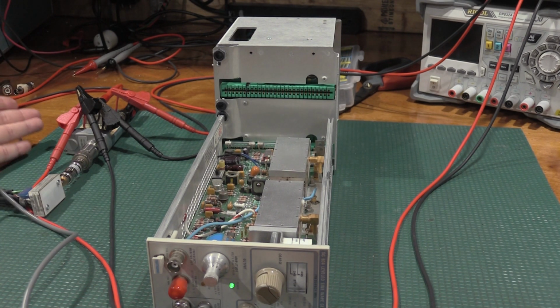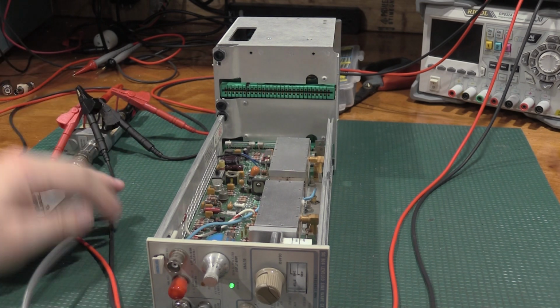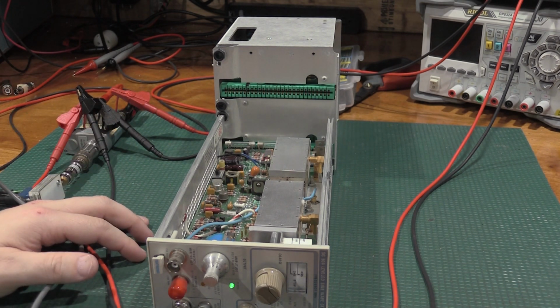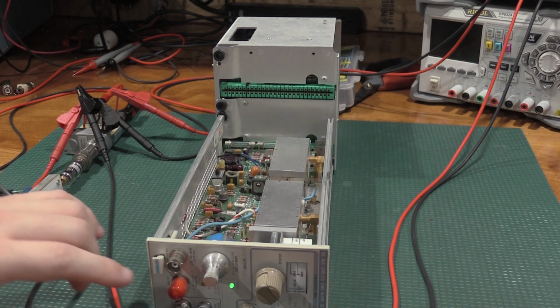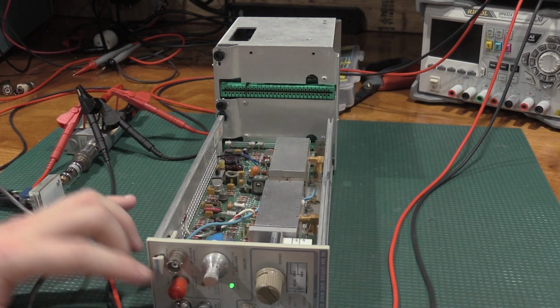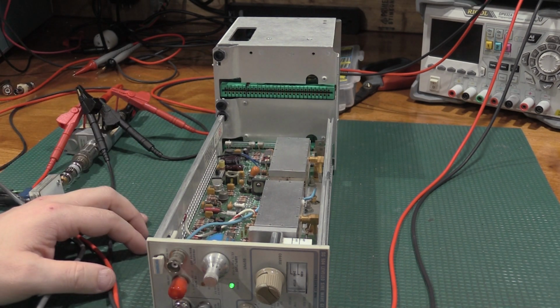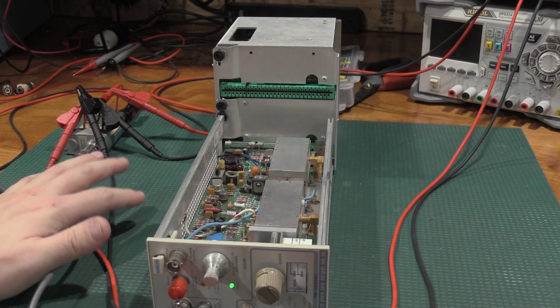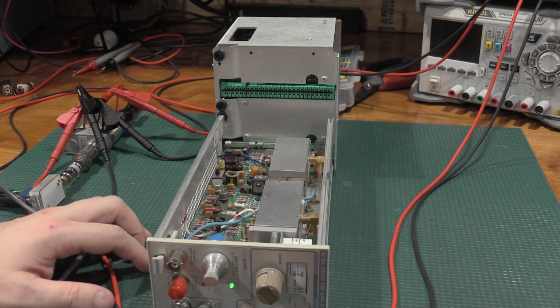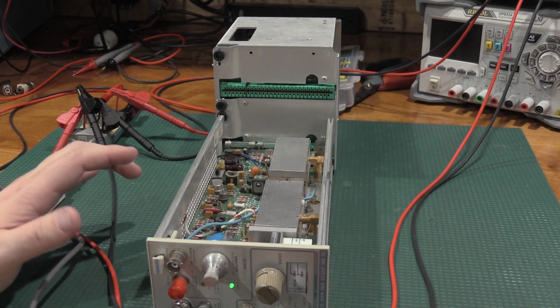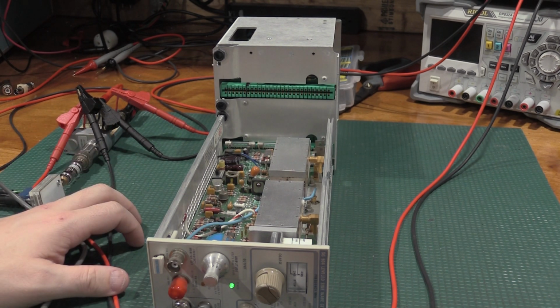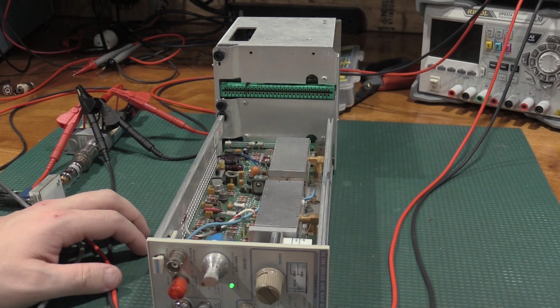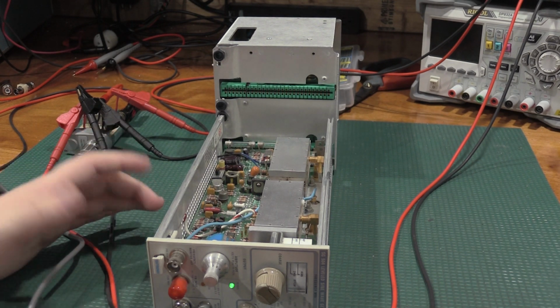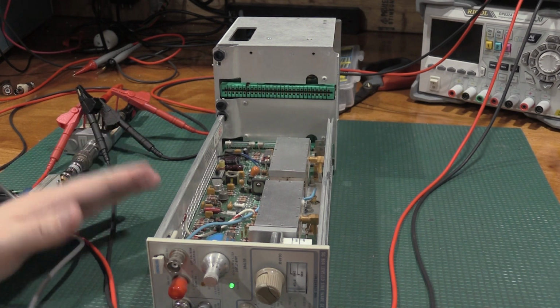This did not work as I expected, but that also means that the SG504 is as verified as I can make it, and I do not get an unleveled light all the way through the bands. So pretty sure it's working. I'm going to double check the low end range on my DSA because I'm well within the 1 gigahertz measurement capabilities. But so I'll run through that. But if that checks out, the low range is at least good.